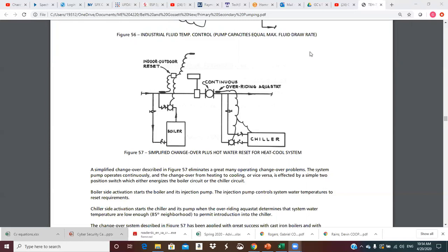If you're coming off of heating, you have to turn off the boiler, keep the chiller off, and just circulate the continuous pump through the loop. Heat losses — and possibly some areas still doing a little heat — will eventually cool the water down to where it's safe to put into the chiller. That's what the overriding aquastat is for. Likewise, you have to be careful about putting too cold water into the boiler. So whether this is an automated system or manually operated, whoever is turning on and off the pumps needs to check the loop temperature before changeover.